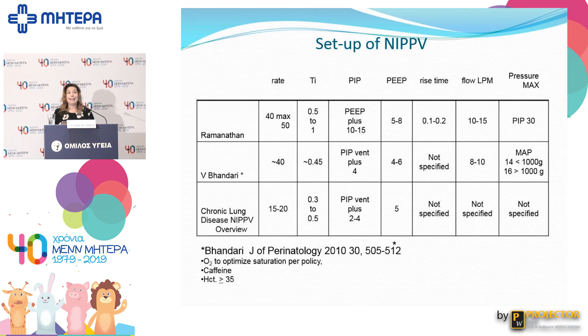The flows in each of these first two studies were set on those ventilators for those studies. Now that we're using variable flow ventilators most commonly, we're not deciding on the flow. We're deciding on the PEEP, and we're deciding on what that upper number is in NiPPV, and the device is using whatever flow it needs to deliver that. How you set a default pressure max, you can set it by the mean airway pressure, or you can set it by an upper peak. But pretty much across the board, most people are suggesting setting it up about the same way.